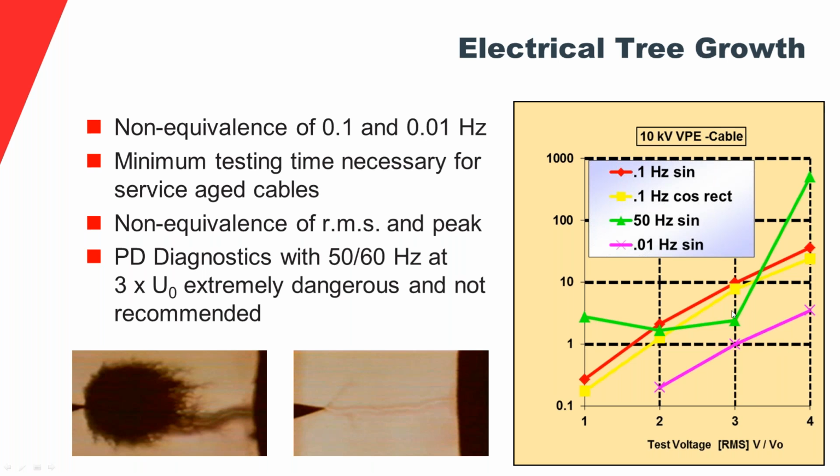And the reason is in this diagram. I mean, this is nothing new. This is published since many years. Why that continuous 60 hertz, when you do the PD diagnostics, why that causes problems because of these water trees that you grow.